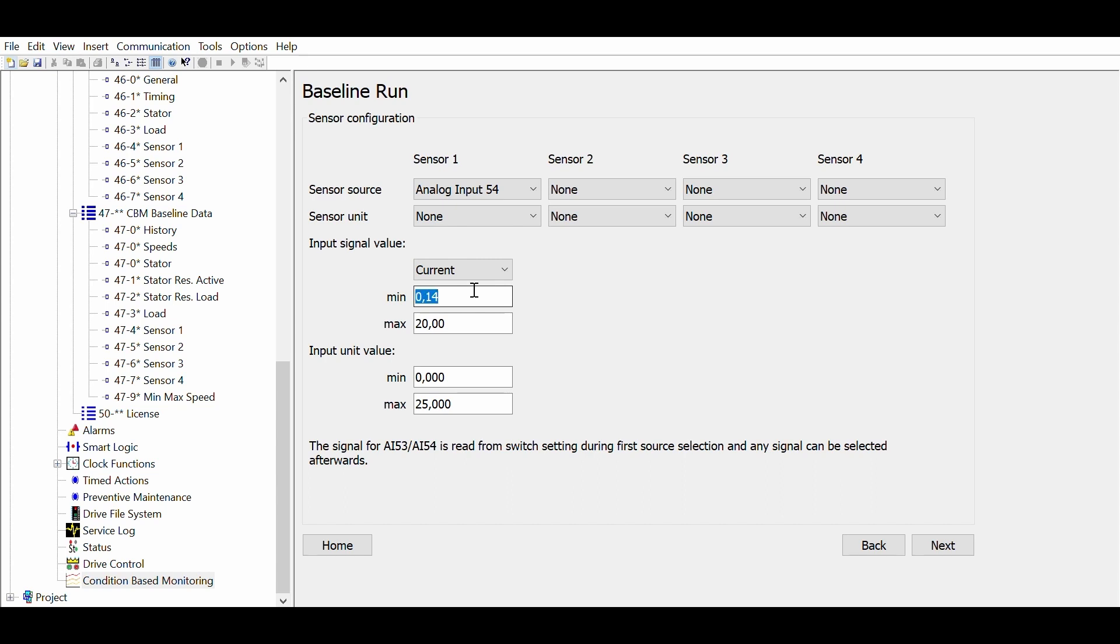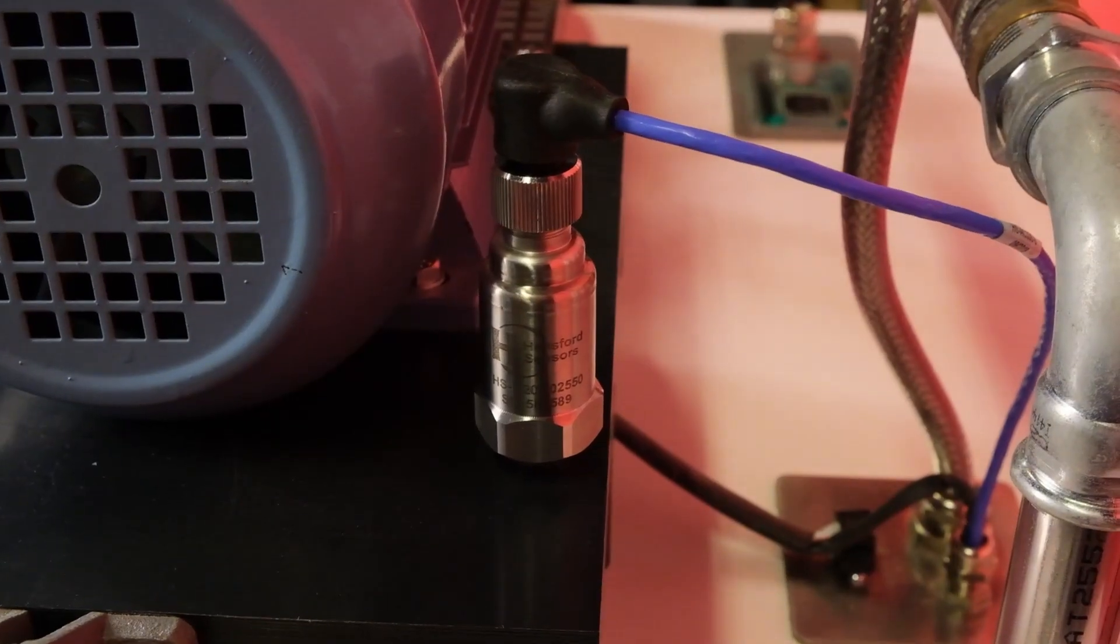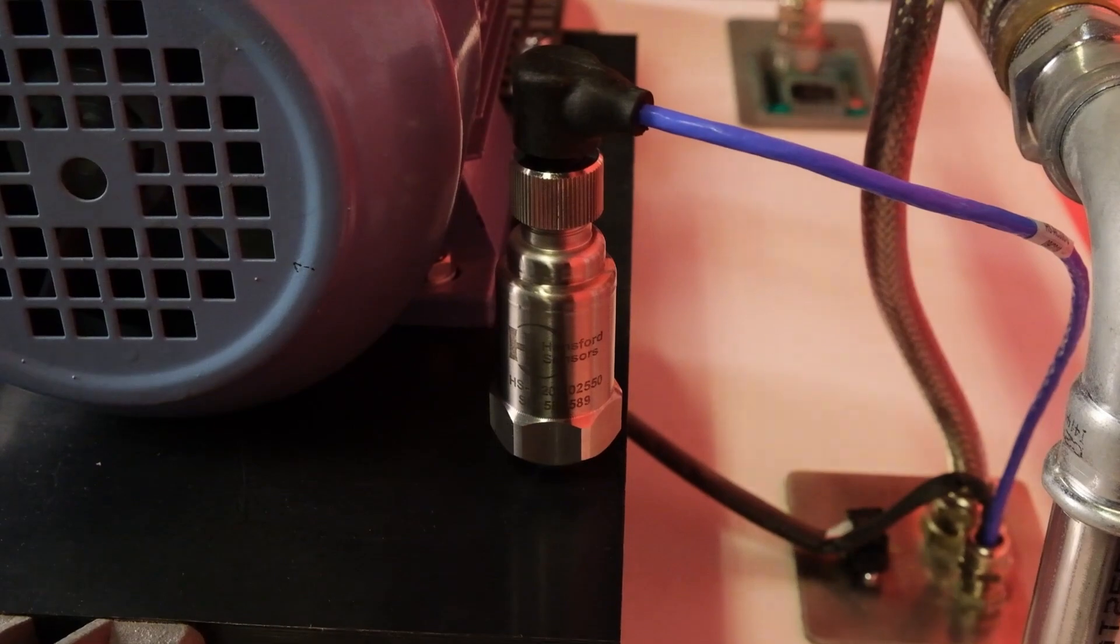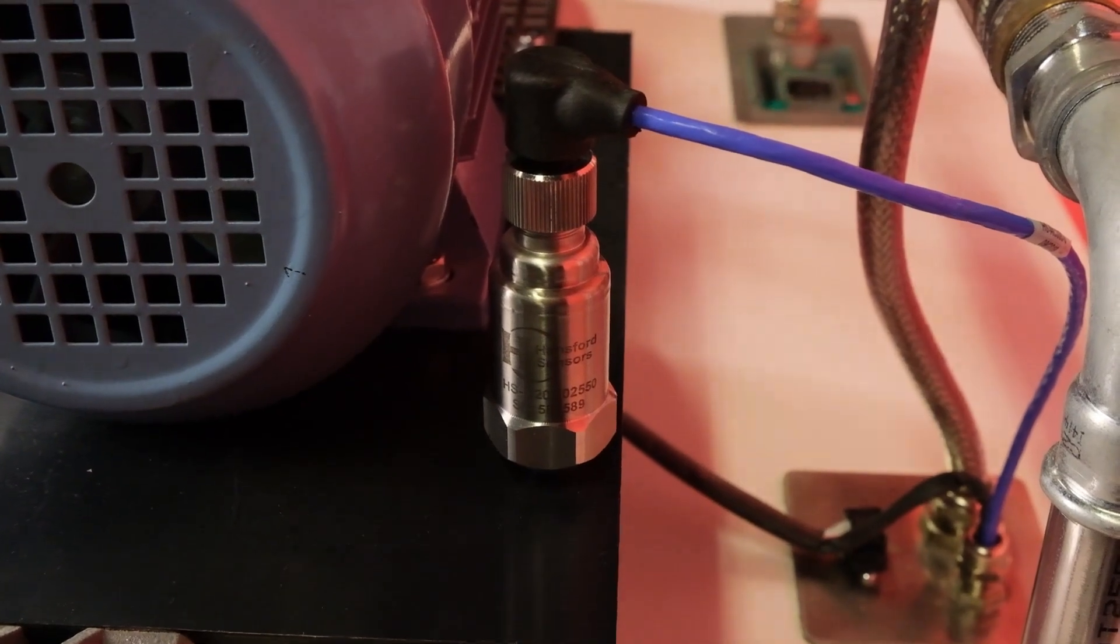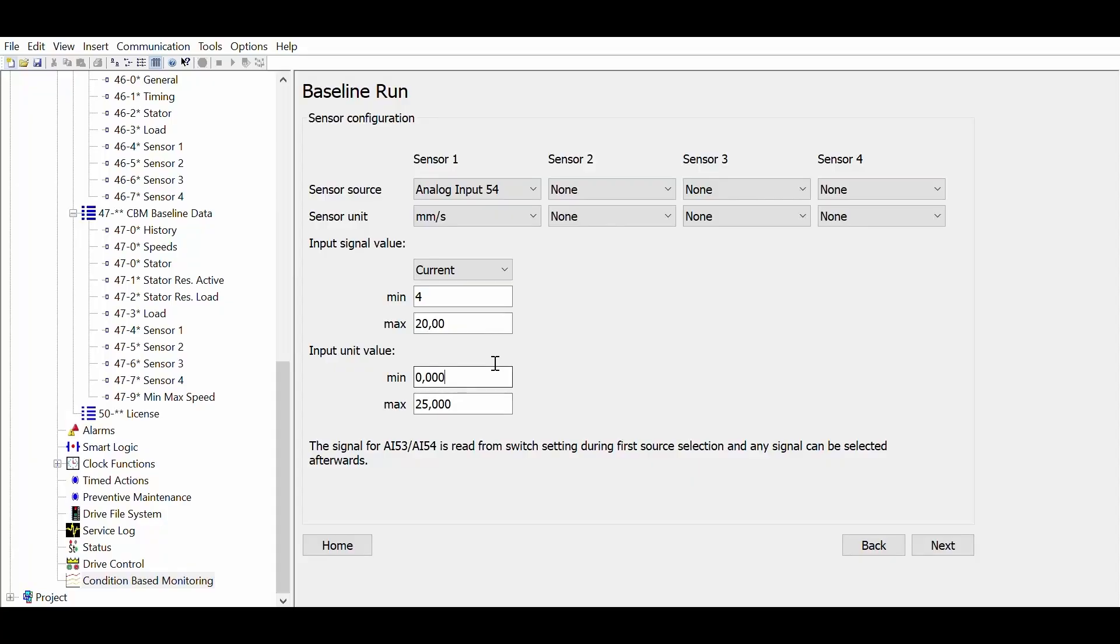We will now set sensor 1 to analog input 54. We need to set the scaling of the sensor, which can be found either written on the sensor or in the sensor datasheet. In our case we have a 4 to 20mA vibration sensor with the measurement range of 0 to 25 mm per second.